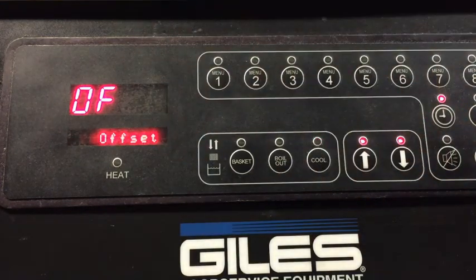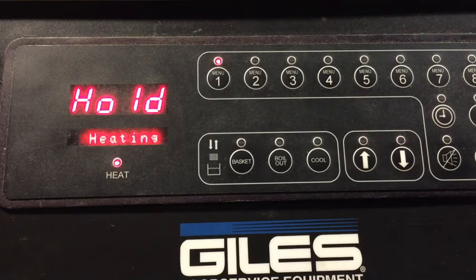Offset is OF. This is your calibration factor. It should typically be OF, 0, no calibration factor at all. If you have some kind of problem that you have to put one in, never adjust it more than 10 to 12 degrees, because the more you adjust it, as the temperature widens, so does this gap, and it'll get farther off. Typically not even something that you have to worry about, but if you get a store that is really particular and wants it down to that exact science, then you could have that problem. Now you see what happens if we don't do anything. If we don't touch any keys for 20 seconds, it'll go ahead and fault out.